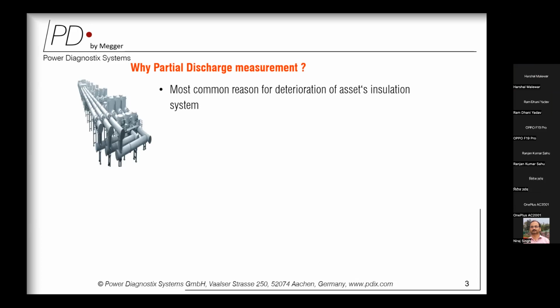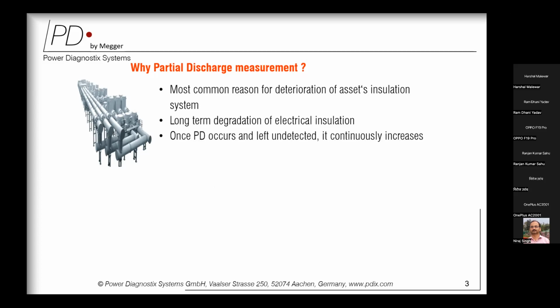Partial discharge is the most common reason for deterioration of an asset's insulating system, because everything we do in today's modern world about measurement in electrical assets is to keep our insulating system intact. If the insulation is good, the system will operate for a prolonged period of time and there will be fewer hassles in the operation. When partial discharge occurs, it gets associated with long-term degradation of insulation. The degradation of insulation starts, and once PD occurs, if it is left undetected, it continuously increases because there is no halt or stoppage. It is a gradual acceleration process.